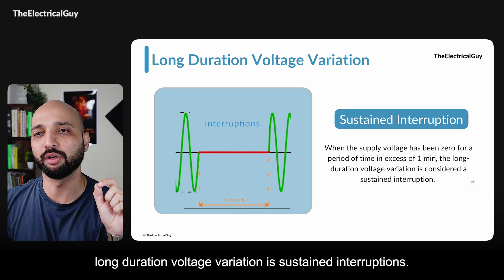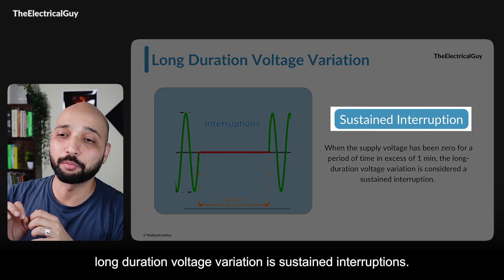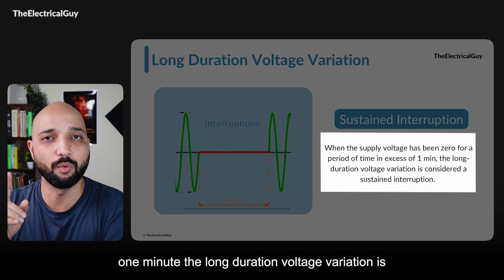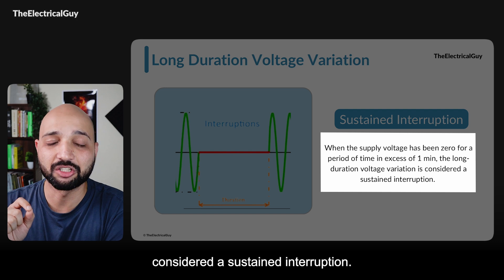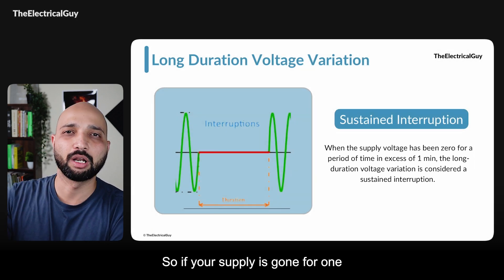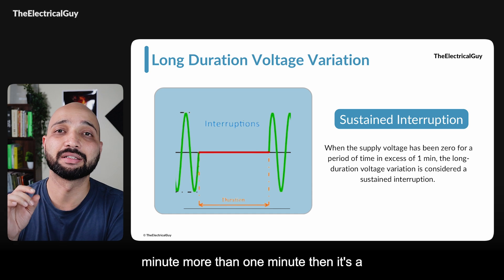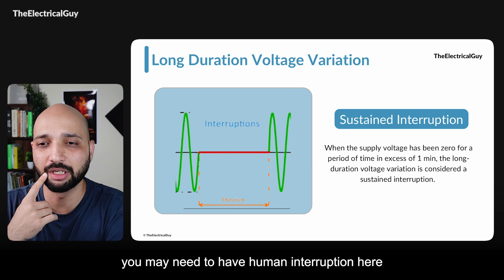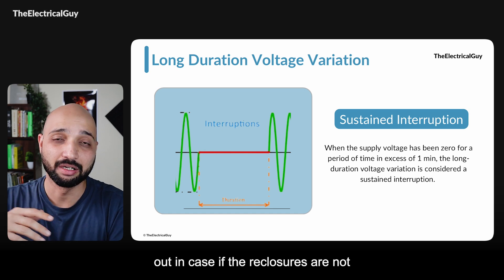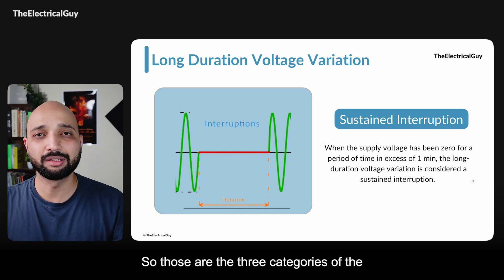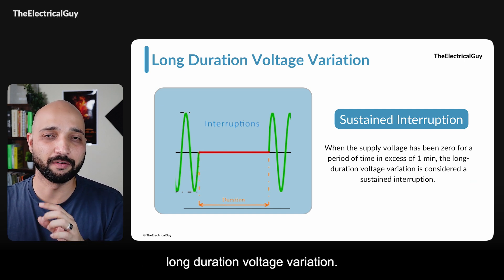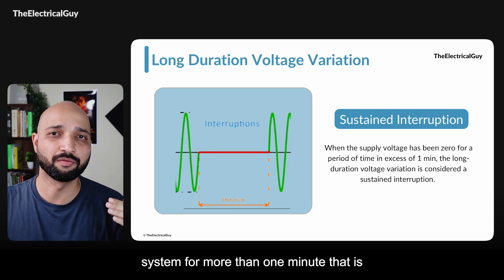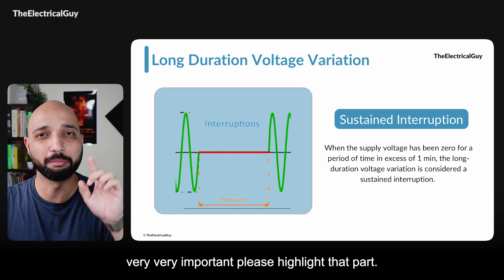The third category in long duration voltage variation is sustained interruption. When the supply voltage has been zero for a period in excess of one minute, it is considered a sustained interruption. If your supply is gone for more than one minute, it is a sustained interruption, and you may need human intervention to identify the issue and clear it, especially if reclosers are not in place. The important point is all these scenarios remain in the system for more than one minute.